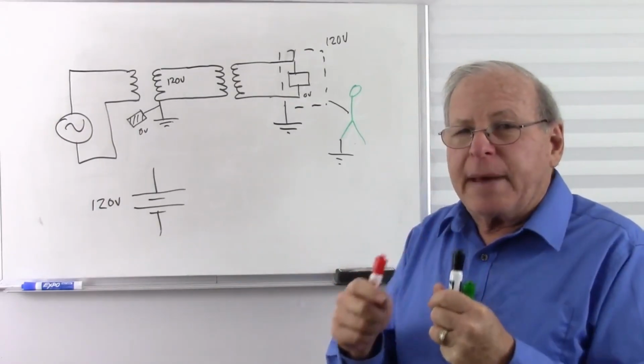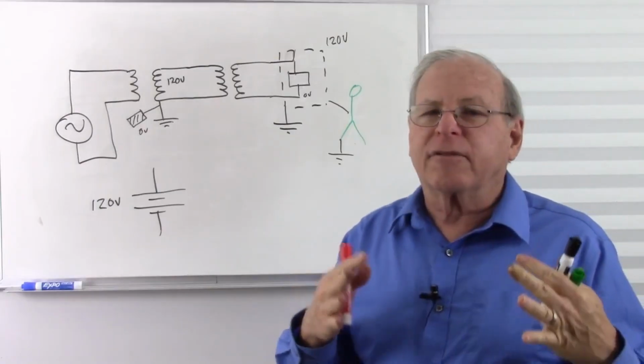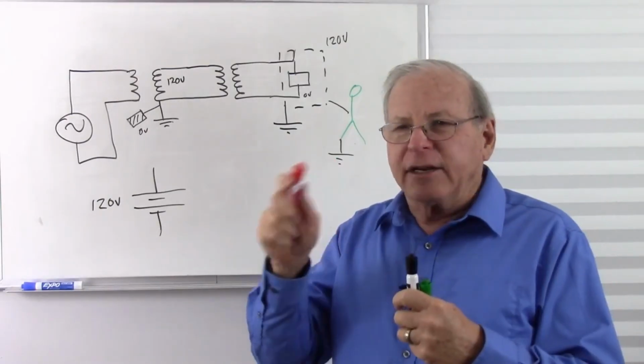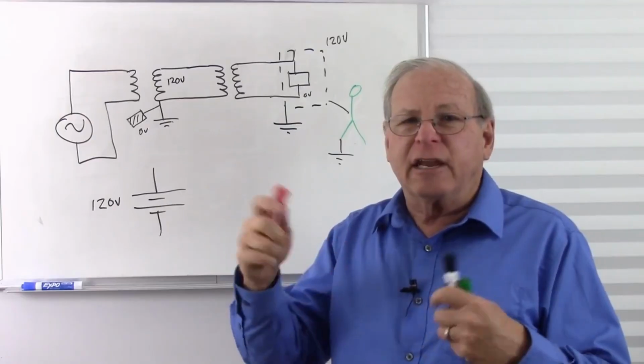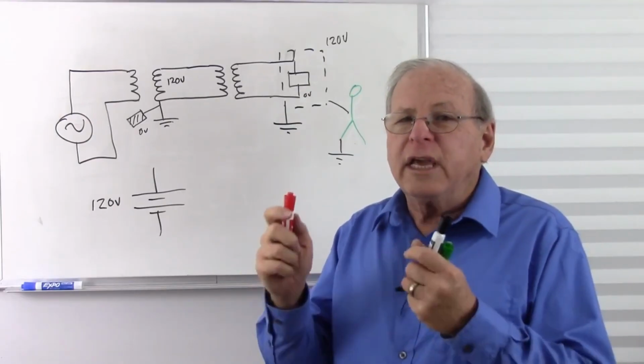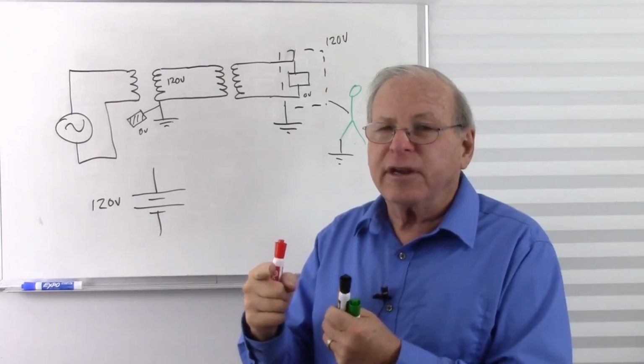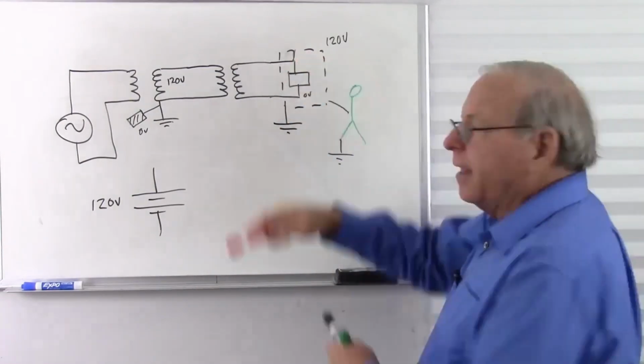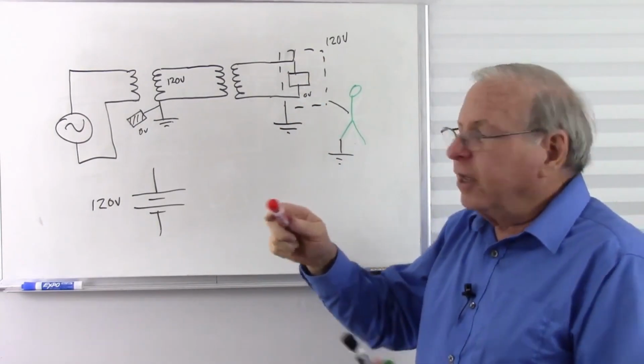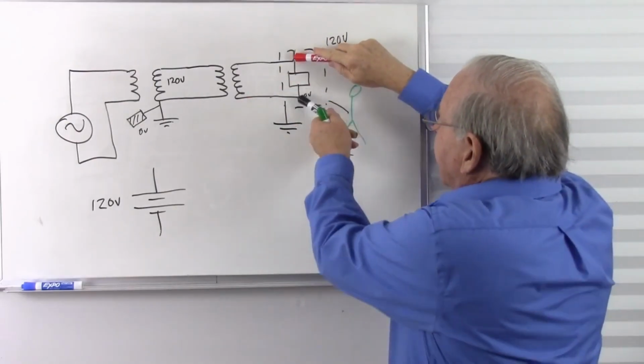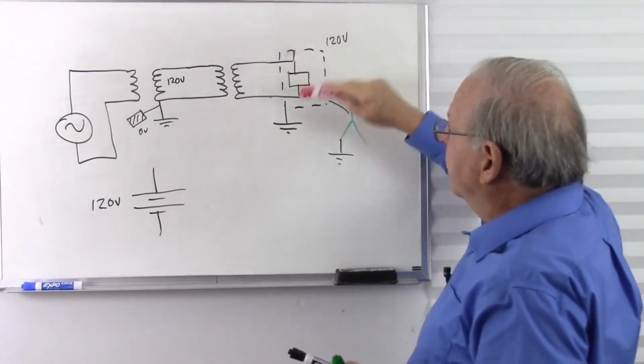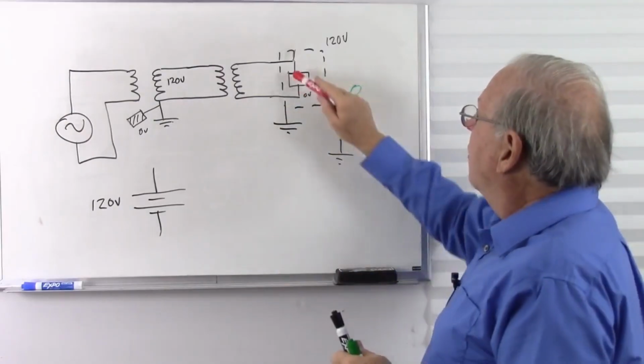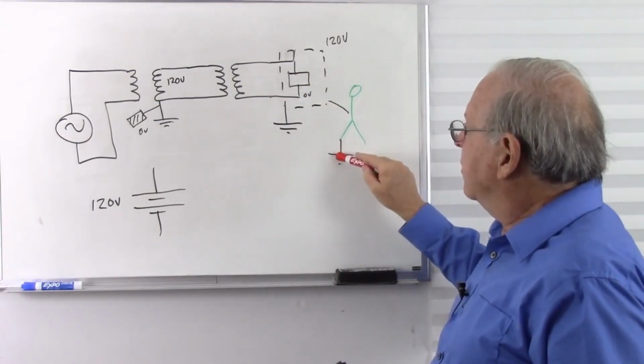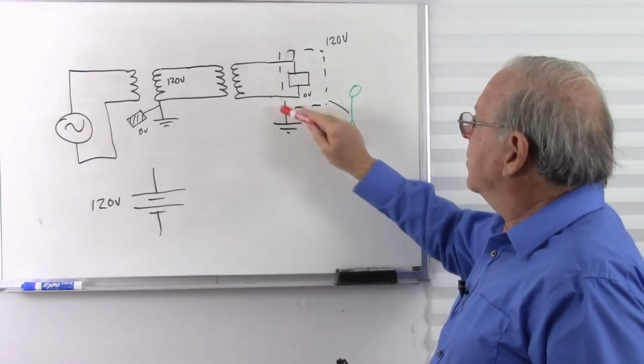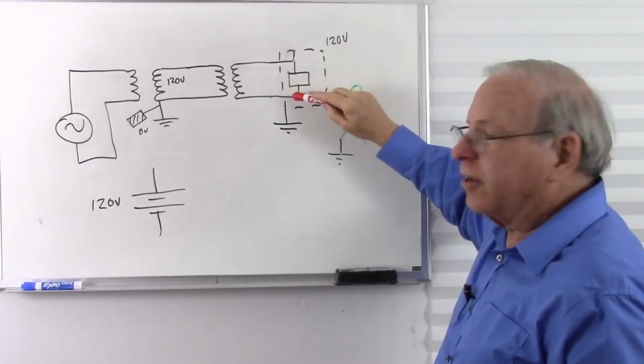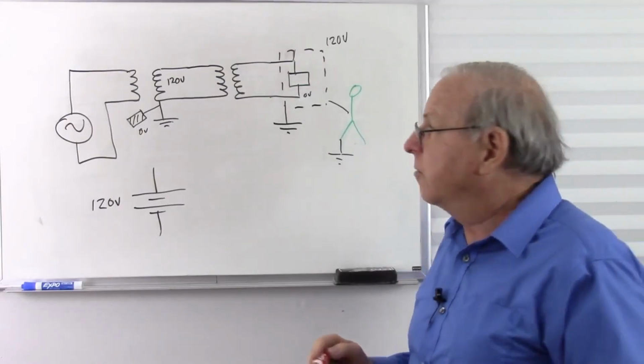Take one side of that battery and connect it to ground. Find something that has a grounded chassis and test that battery. Touch the positive, touch the negative. Do you get any reading? No. Only if you have a connection from the positive to the negative. We have the same thing here. The only way I'm going to get any kind of a measurement is if I connect to that side and that side. That's what it's referenced to. This ground is irrelevant. So I've got the fault. I'm connected to ground. This is connected to ground, but the ground is irrelevant to the circuit because I have to somehow be connected to that side of the transformer too.